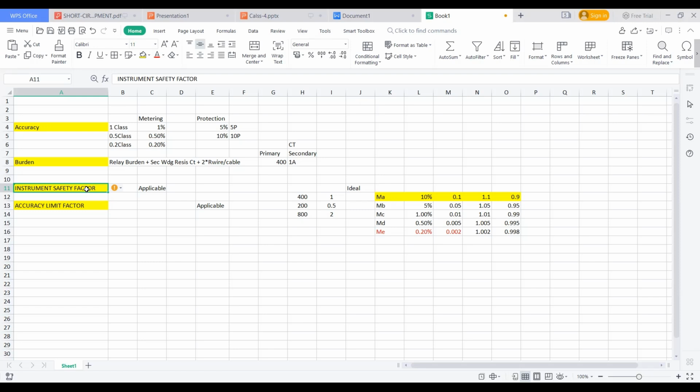Generally, the guideline as per IEC 61869 for CTs is that the instrument safety factor for metering should be less than or equal to 5. This is the condition. The ISF is the primary side fault current to the rated primary current.